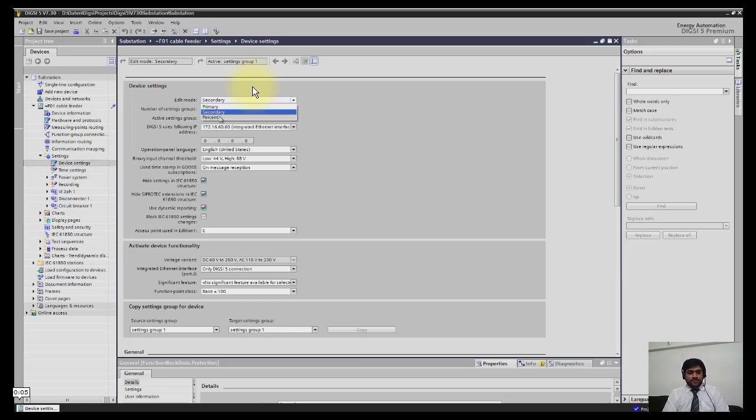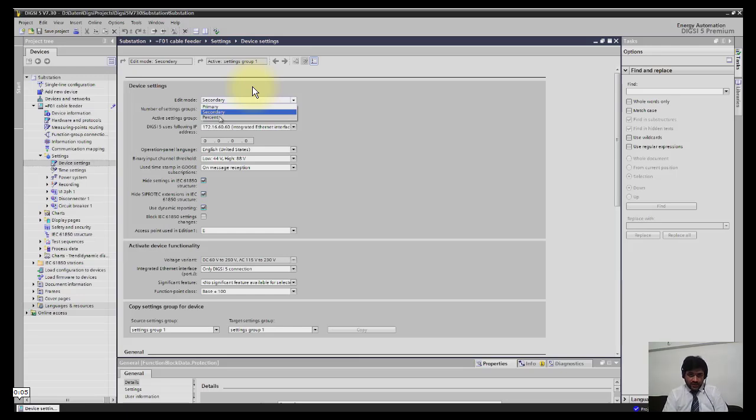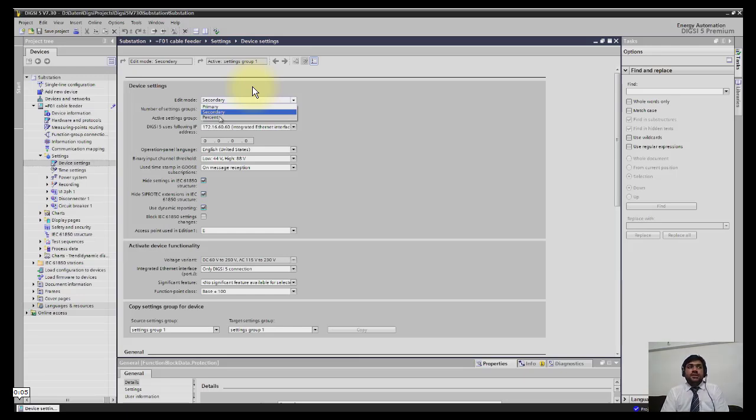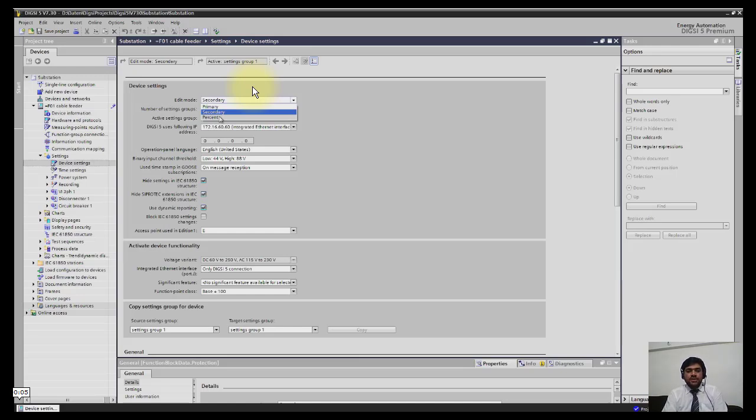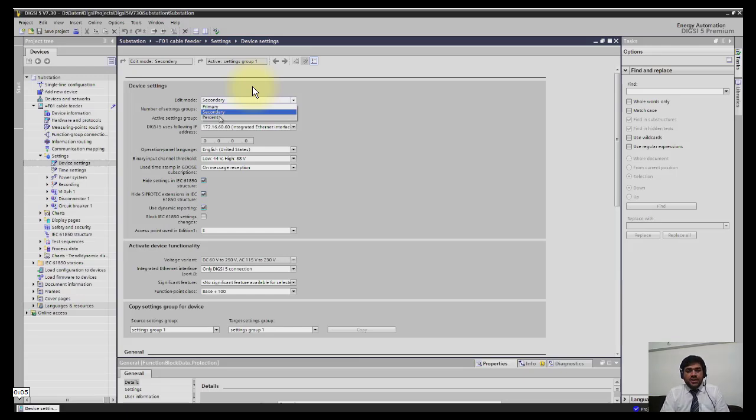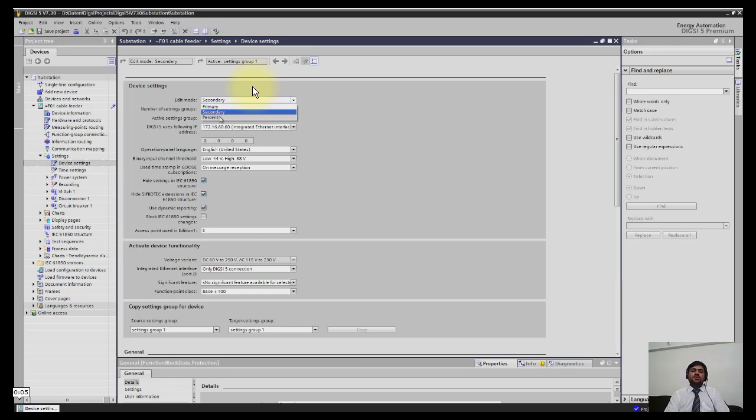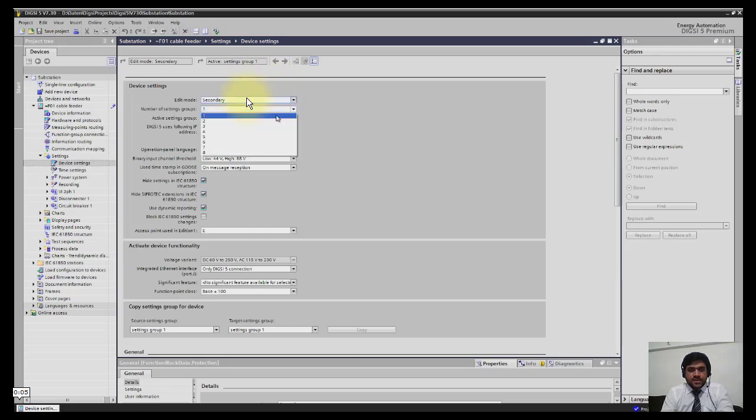In DIGSI 5, all values are entered on the secondary side, which is normal practice. For example, if you have a CT of 800:1 and want to select that at 800 ampere the relay trips, if you select secondary, you write the pickup value 1 ampere. If you select primary, you write 800 ampere. If you select percentage, you write 100%.